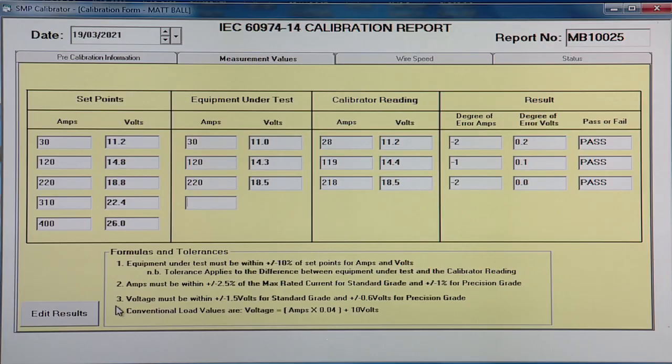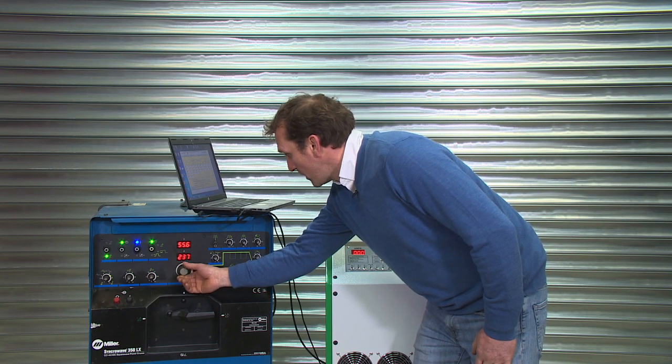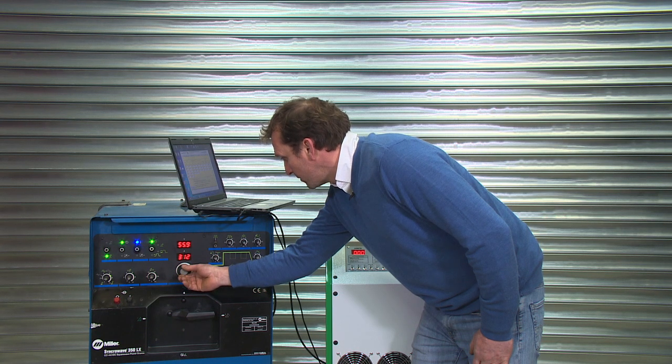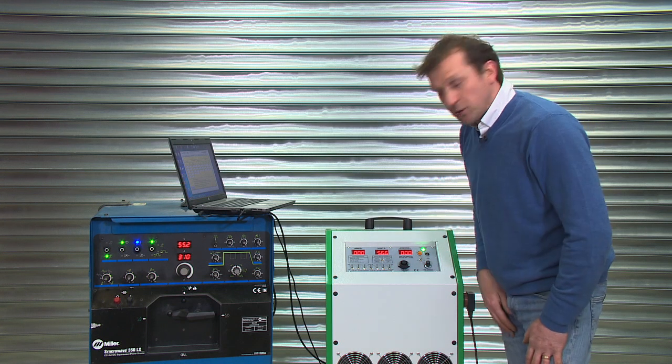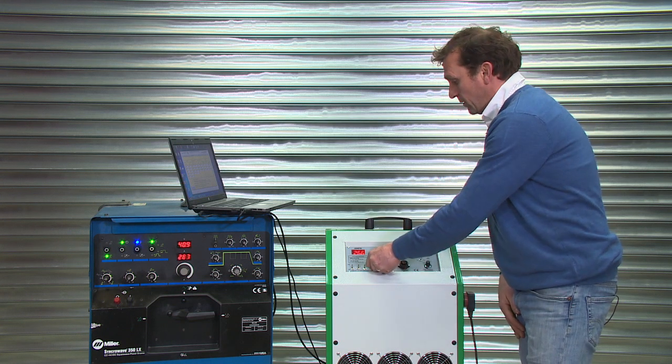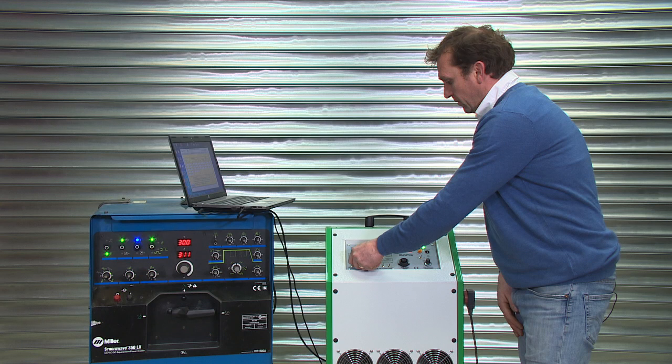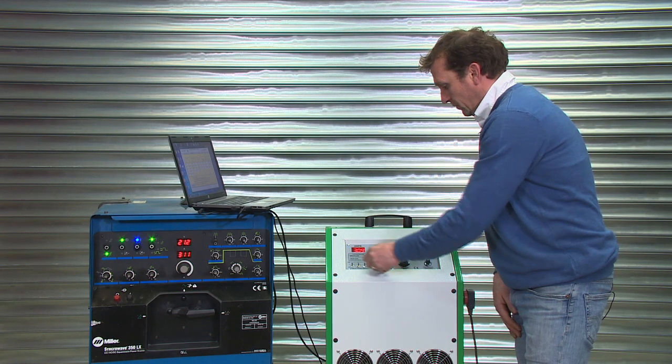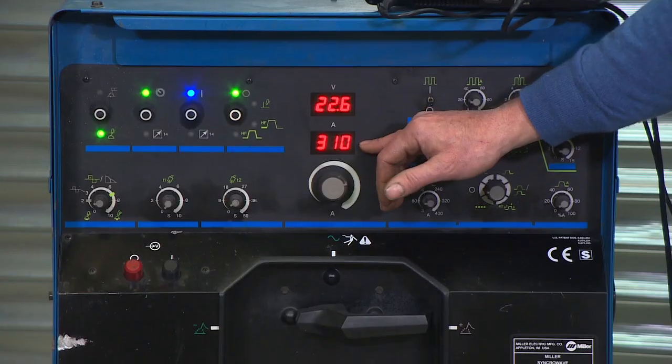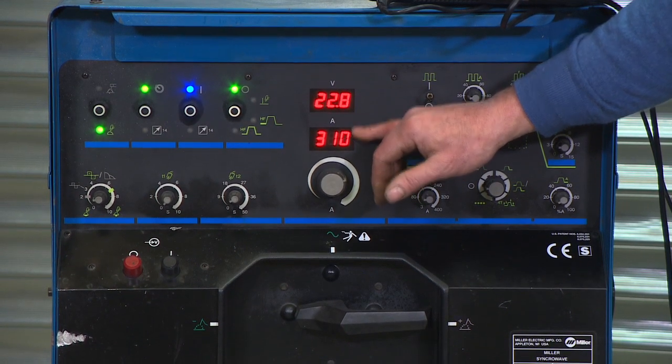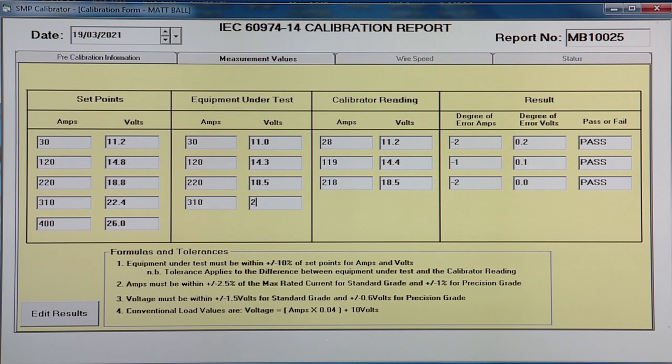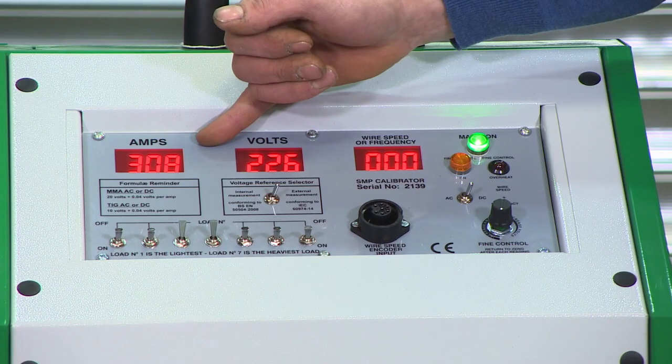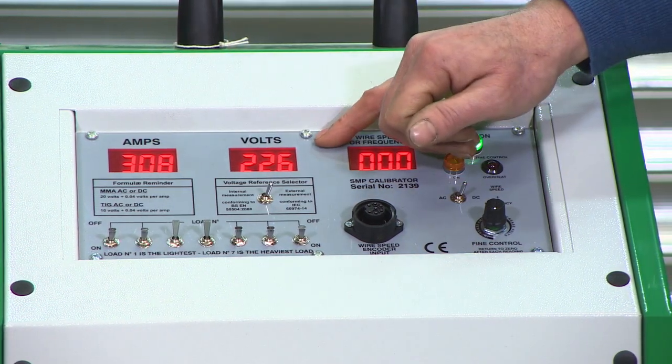And then we'll take our penultimate reading of 310 amps, 22.4. So we set the machine, the welder to 310. And load the calibrator to approximately 22.4. We'll record the welder reading of 310 amps, 22.6. And then the calibrator reading, 308, 22.6.